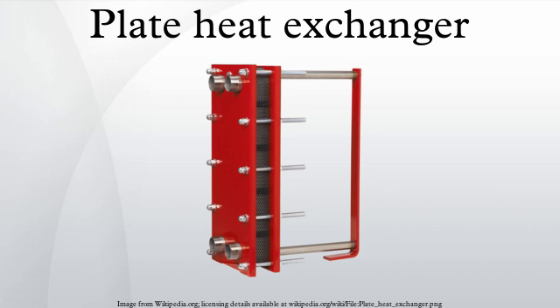An important aspect to take into account when evaluating a heat exchanger is the form of corrugation within the heat exchanger. There are two types, intermating and chevron corrugations. In general, greater heat transfer enhancement is produced from chevrons for a given increase in pressure drop, and they are more commonly used than intermating corrugations.